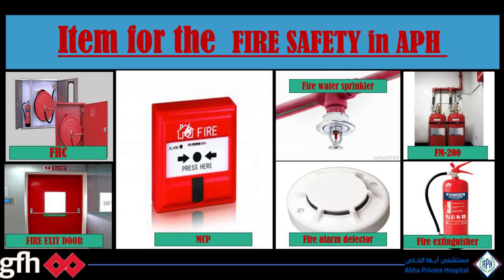Fire alarms are essential devices that detect smoke or heat and promptly alert occupants, allowing for a quick evacuation. Fire pumps are critical in maintaining water pressure in the fire sprinkler system, ensuring a steady and reliable water supply to extinguish the flames. These systems often include components like control panels, sprinkler heads, valves, and piping, all working together to prevent the spread of fire and minimize damage. Proper maintenance and regular testing of these systems are vital to ensure their effectiveness in an emergency.